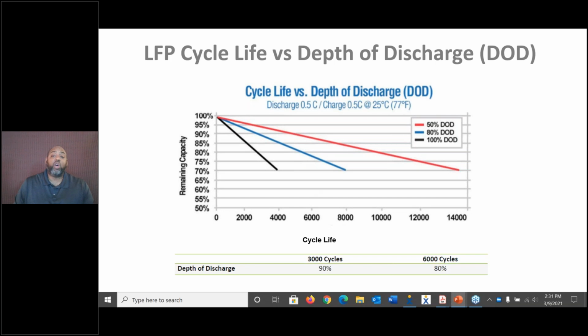If you notice, if you go to 100% depth of discharge, look at the life cycles - it drops pretty drastically. Lithium phosphate batteries can literally be discharged faster. That's not a problem, but if you discharge it faster, you're just shortening the cycle life of the battery. That's something you need to make the customer aware of. If you discharge this battery at the rate of a flooded lead acid battery, you'll notice the discharge rate will go a lot farther in cycles. But generally, most lithium phosphate chemistries are designed to be discharged at 80% depth of discharge, 6,000 cycles, 10-year warranty. That's pretty much an industry standard.